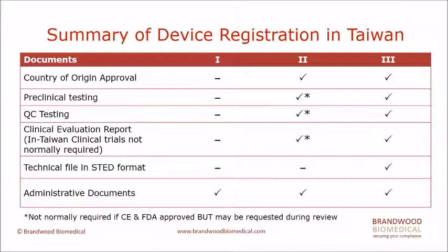This is a summary of device registrations in Taiwan. For Class 1, it's purely the administrative documents. Class 2 requires the administrative documents plus the common documents that we mentioned before, for example, country of origin approval, preclinical testing, and QC testing. The clinical evaluation report is not part of the initial submissions if you have predicates in Taiwan. For Class 3 devices, it's the administrative documents plus the common documents, and also the technical files in the STED format and the essential requirement checklist according to the GHTF format.